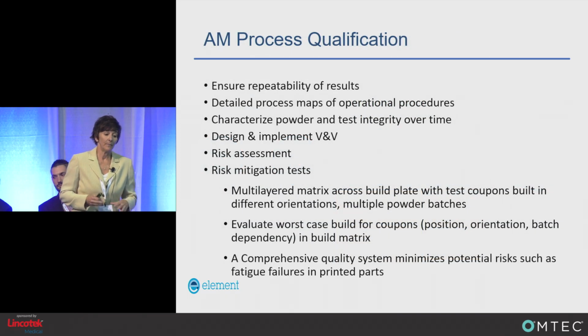And can you revalidate your performance qualification if the designs of that structure may change, the lattice may change, for instance? Then you need to think about qualifying your manufacturing process. This is very important as well. You need to ensure that your results are repeatable. You need to provide these detailed process maps. If they change, you need to document that within your system for your operational procedures. Characterize your powder and test the integrity of the powder over time. A lot of folks will mix that powder. So you need to make sure you can characterize it and test it and ensure that you're going to get repeatability with your product or your coupons.